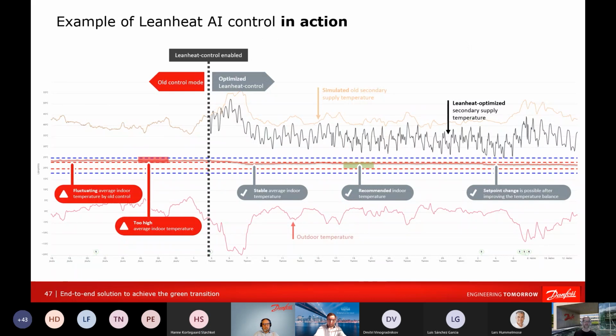Here's an example of how the control works. This is maybe a bit technical, but there's an old control where the supply temperature on the secondary side follows pretty much the outdoor temperature. Then after this black vertical line, the Leanheat control, shown as the black line, is trying to keep the indoor temperature stable.